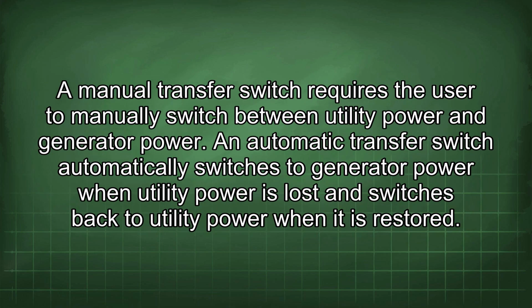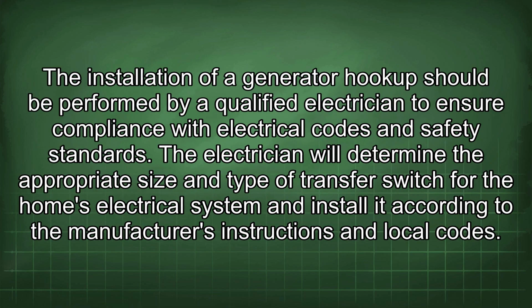A manual transfer switch requires the user to manually switch between utility power and generator power. An automatic transfer switch automatically switches to generator power when utility power is lost and switches back to utility power when it is restored. The installation of a generator hookup should be performed by a qualified electrician to ensure compliance with electrical codes and safety standards. The electrician will determine the appropriate size and type of transfer switch for the home's electrical system and install it according to the manufacturer's instructions and local codes.